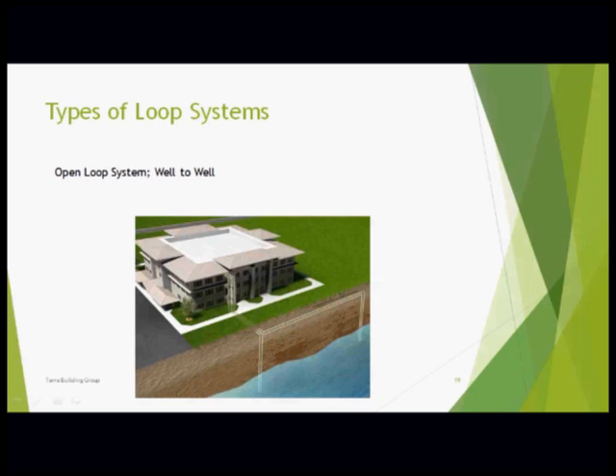They wanted to use this system. What they found after analysis was that they were unable to, because the building sits on top of an eddy. So even though they had plenty of flow for the production well, because they were in an eddy, the discharge well would heat up that water in the eddy, and the efficiency would be reduced. So they had to scrap the plan for their geothermal use.